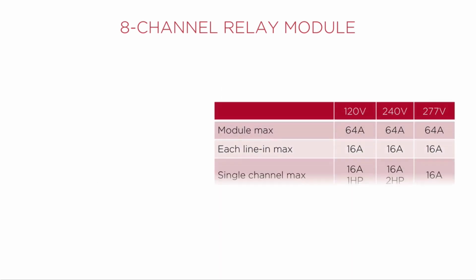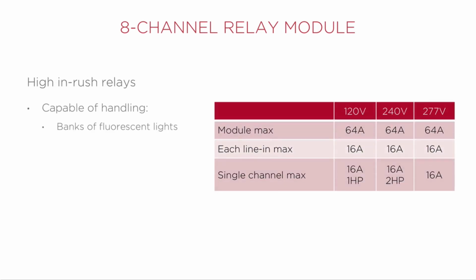The relay module features high inrush relays, capable of handling banks of fluorescent lights, non-dimmable LEDs, landscape transformers, motors, pumps, outlets, etc. At 120 volts, there is a 64 amp maximum per module. Each channel has a 16 amp, 1 horsepower maximum, and at 240 volts, there is a 2 horsepower maximum.